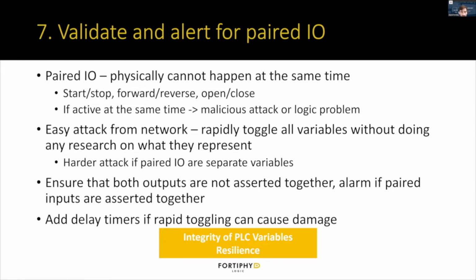Looking at practice number 7, validating and alerting for paired I/O. What we mean by paired I/O is I/O that physically cannot happen at the same time. Something cannot be physically starting and stopping at the same time, in forward or reverse mode, or open or close, at the same exact time. So if the variables are active at the same time, it's either a malicious attack, the attacker just blindly messing with things, or potentially a logic problem.